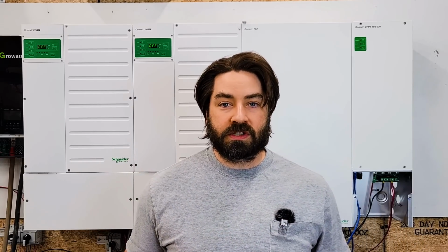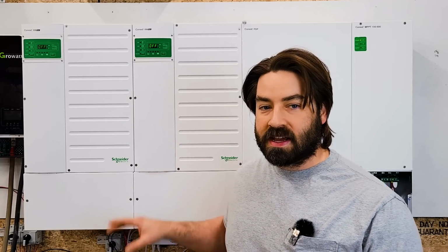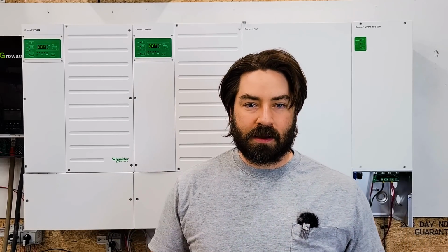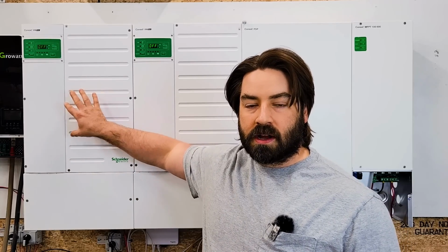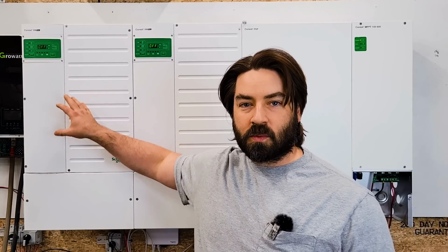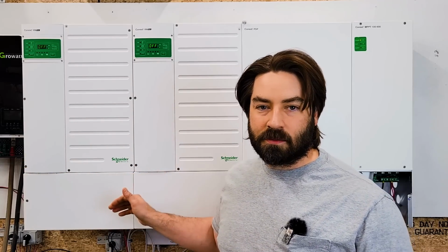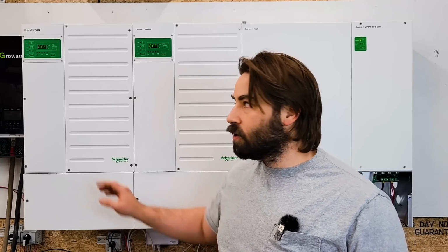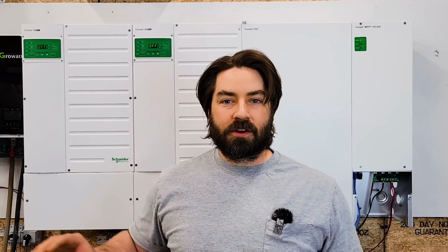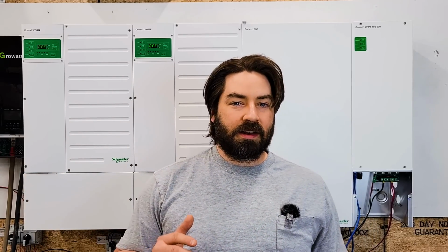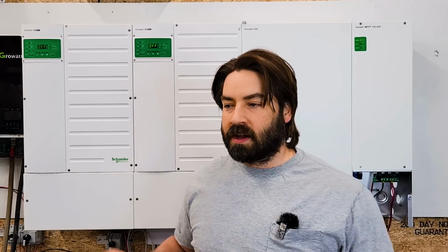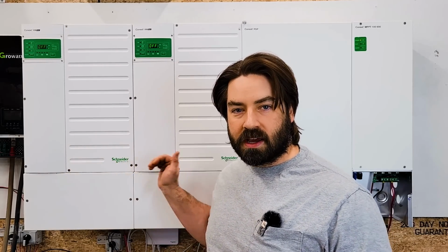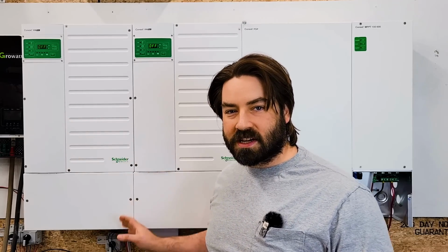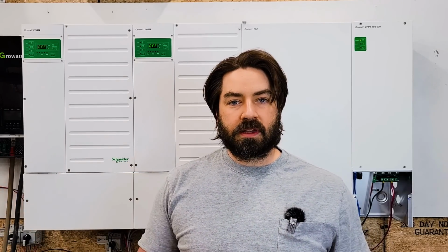So once all the hardware is done, now it's time to program things. And this is where I probably should have waited on that data cable. I needed to program this inverter, but it was in fault mode because it wasn't set up right. So what I did was I disconnected the communication cables. I ran from the Insight Home directly to this one inverter, and that way I could change all the settings in this inverter and get it all correct before paralleling. I didn't realize that there might be another way that Schneider has to do it, but I struggled with that a little bit because I had them all communicating and it was in fault mode. Once I changed it, so just the Insight Home was talking to just this one inverter, it was not in fault, and then I could update the firmware in it.